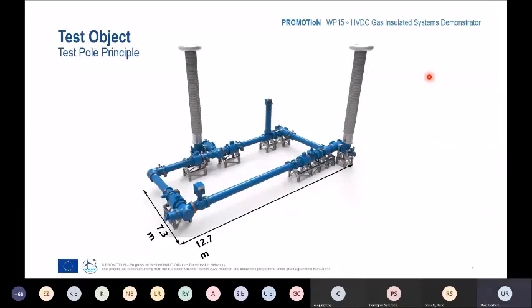Here you can see the test device, the HVDC GIS, which is rated for 350 kV DC. The test device itself for this long-term test was defined in our work package. At the end, it is a 13 by 7 meter ring arrangement. We have one bushing to connect the voltage sources, so the DC voltage source as well as the impulse voltage source from the lab.